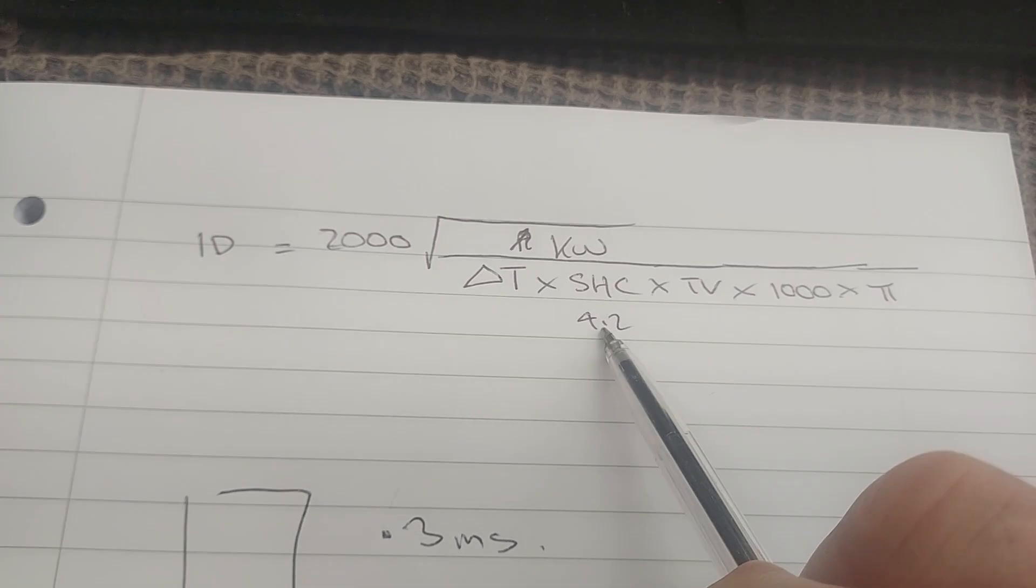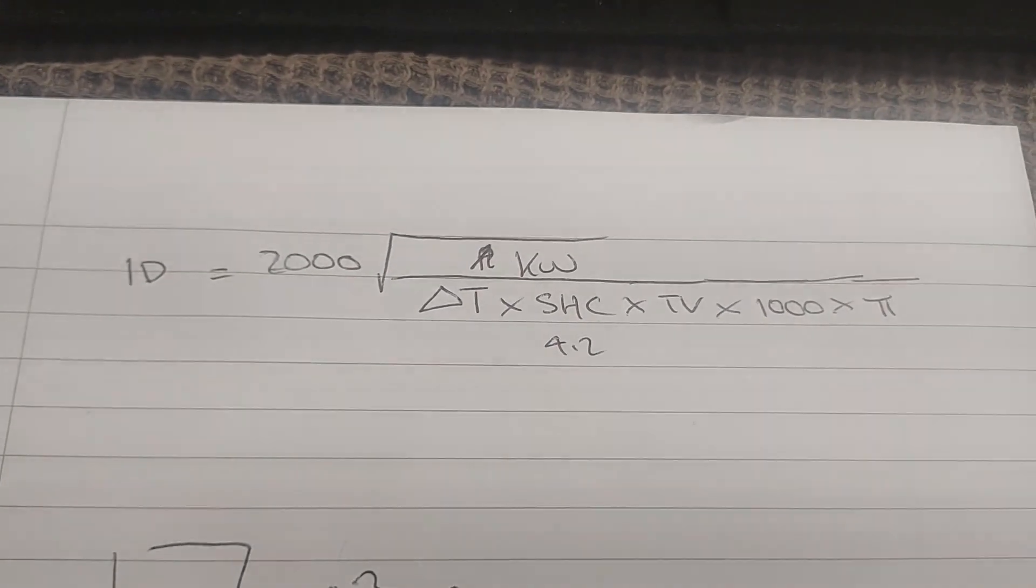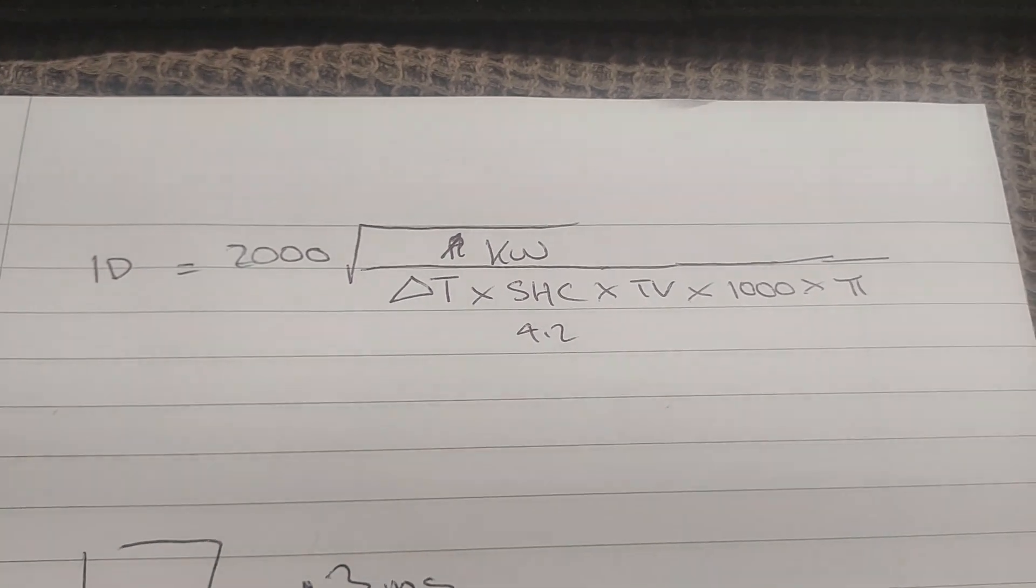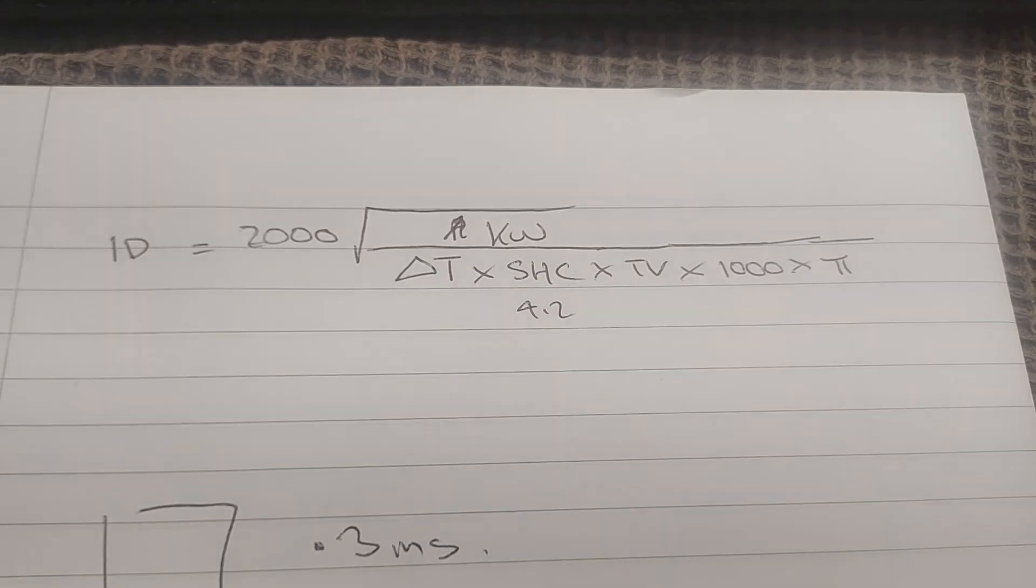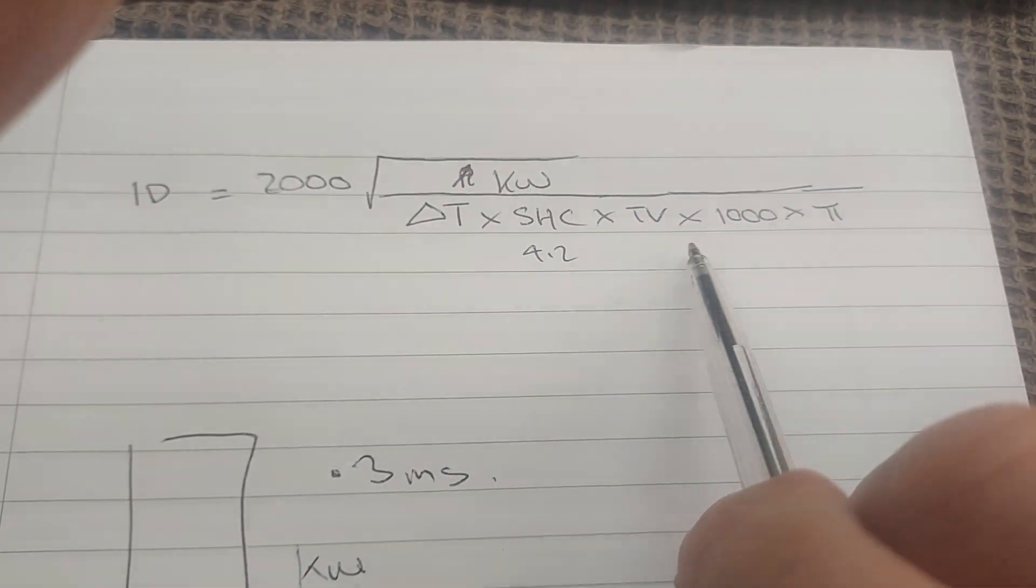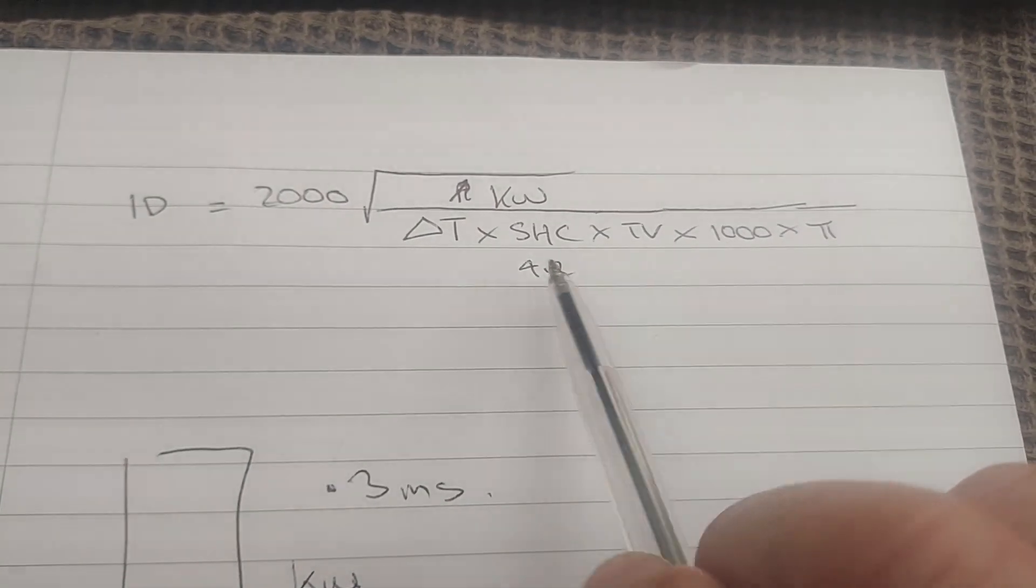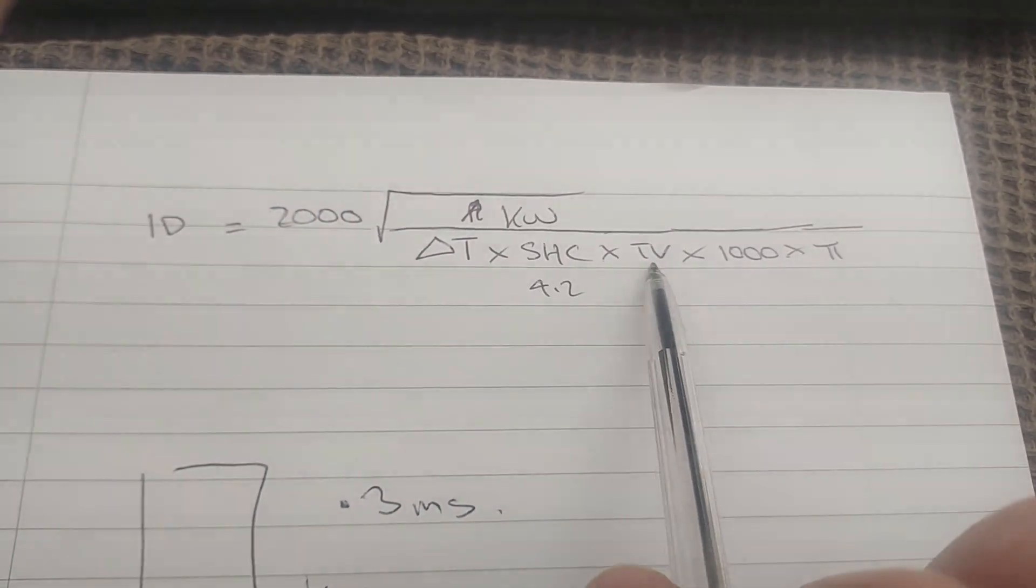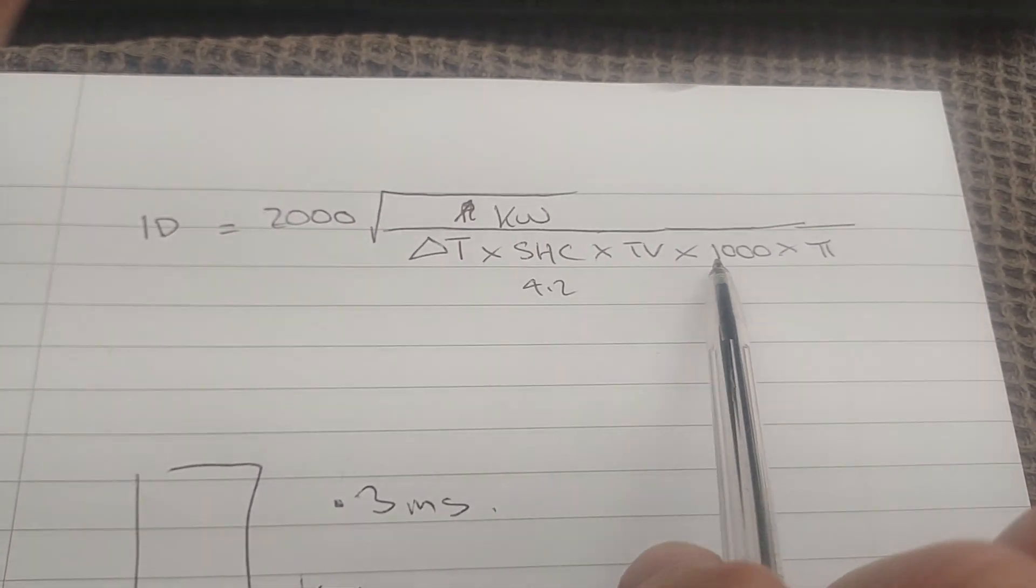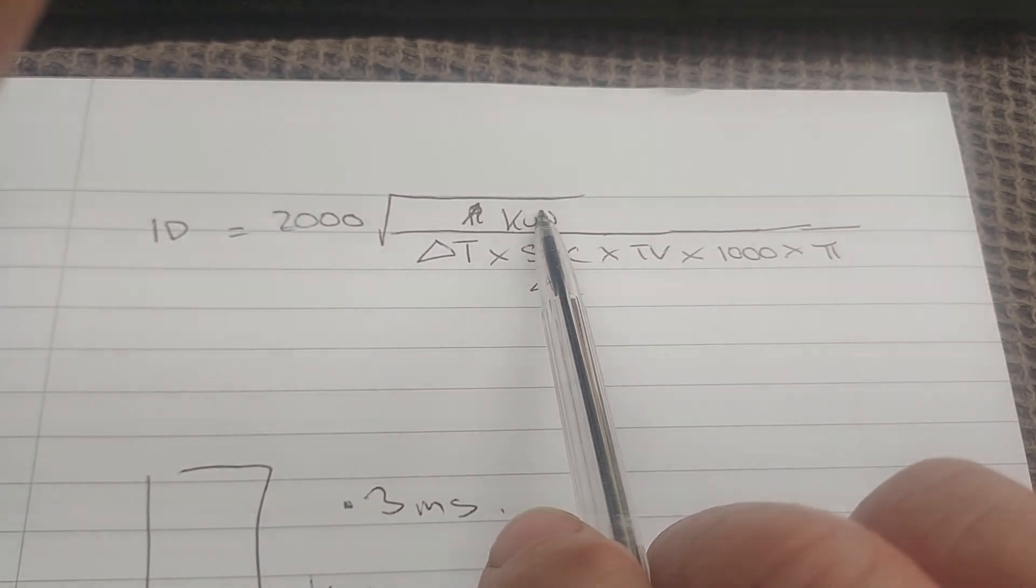Specific heat capacity if you're in kilowatts is 4.2. If you're going to do this in watts then your specific heat capacity will be in joules and not in kilojoules. Target velocity is always in meters per second. The 1000 and the 2000 are just conversions to help us deal with the interaction between millimeters and meters. This answer is in millimeters, but we've got meters per second in velocity.